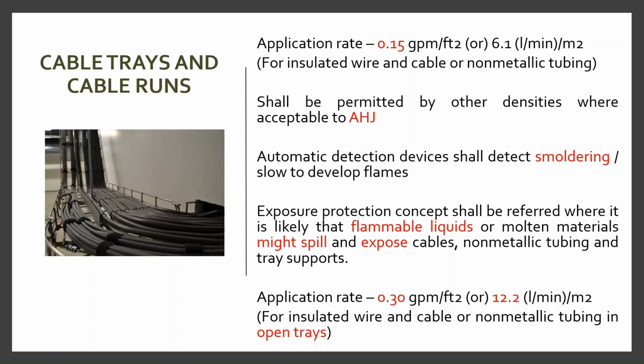So let us understand the basic rules for protecting a particular cable tray. As we already discussed, cable trays requires the protection as well, especially in substations. So let us look point by point. If you look at this particular screen, we have mentioned like the design density rate shall be 0.15 GPM per square feet if we have the insulated wires and cables or non-metallic tubing. And we can consider the other design densities as well upon approval from authority having jurisdiction or local authority.